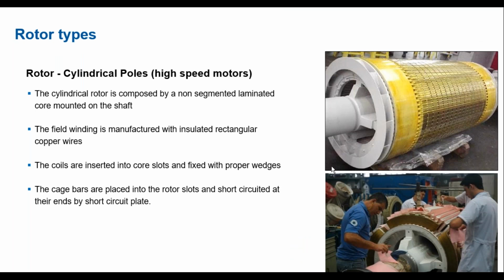Just to show you a little bit more detail on the construction, the cylindrical rotor is composed of a non-segmented laminated core mounted on the shaft. The field winding is manufactured with insulated rectangular copper wires. The coils are inserted into core slots and fixed with proper wedges. The cage bars are placed into the rotor slots and short-circuited at their ends by short-circuit plates.